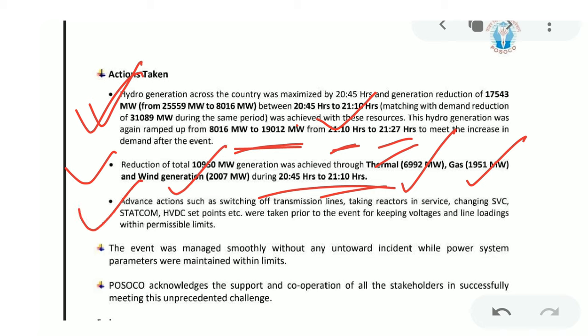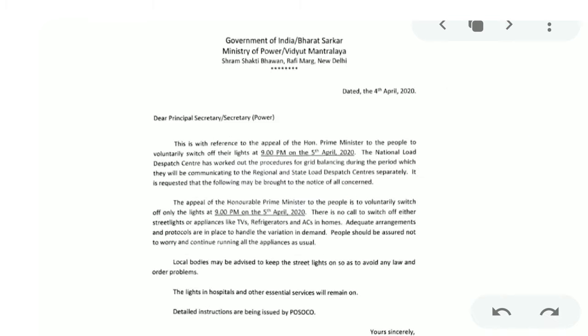Advanced actions such as switching off transmission lines, taking reactors in service, changing SVC, STATCOM, HVDC set points were taken prior to the event for keeping voltage and line loadings within permissible limits. Now, there was also a chance that if everyone turned off their entire load, that fear was also there, because that would result into a sudden spike in the reactive power demand as well once the event gets over. As you can see here in this letter, they have pointed out this.